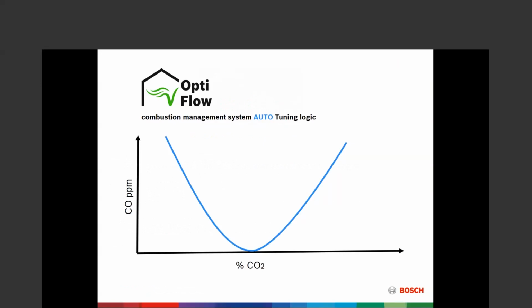So OptiFlow, we talk about automatic tuning. Typically when we talk about setting up burners on a modulating burner, we want to set those up with a combustion gas analyzer, a flue gas analyzer, in part because we want to make sure that our carbon monoxide levels are low so that it's safe, but more important, so that we hit that perfect stoichiometry. And we're going to do that by measuring this percent CO2 in the flue gas. One of the things that makes it sometimes difficult in doing that is if your CO is fairly high.